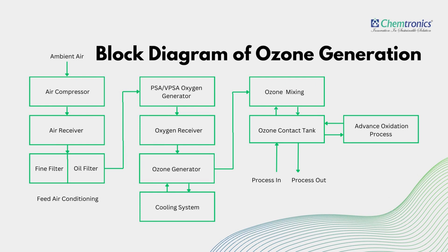First, ambient air is compressed and stored in an air receiver. Then it is filtered for any physical particles, dust and oil, and fed to the oxygen concentrator. The oxygen concentrator works on vacuum pressure swing adsorption. This oxygen is stored in a receiver, and from here, oxygen is fed into the ozone generator, producing a high ozone concentration. The water cooling system provides necessary cooling to the ozone generator.